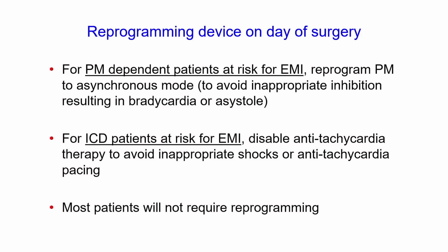There are some patients that will need their device reprogrammed on the day of surgery. Really two groups of patients. So first group, patients who are pacemaker dependent, who are at risk of EMI, should have their device reprogrammed to an asynchronous mode to make sure that they don't have inappropriate inhibition resulting in bradycardia and asystole. For defibrillator patients at high risk of EMI, they should have their device reprogrammed to prevent inappropriate shocks and anti-tachycardia pacing. Keep in mind that most patients will not need to have their device reprogrammed, but these two groups of patients will. And so let's go through the algorithm.